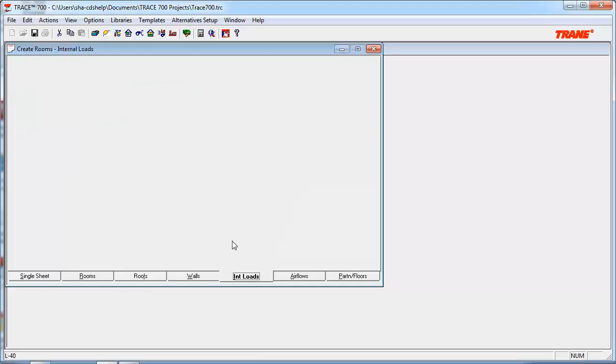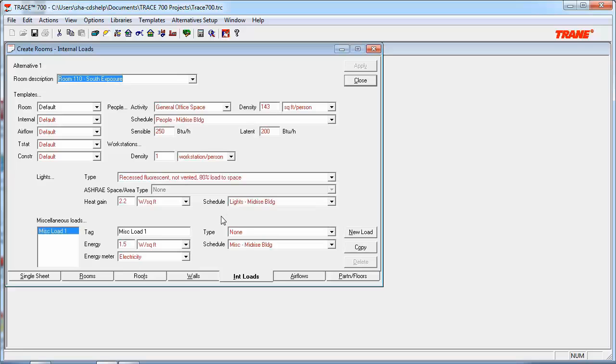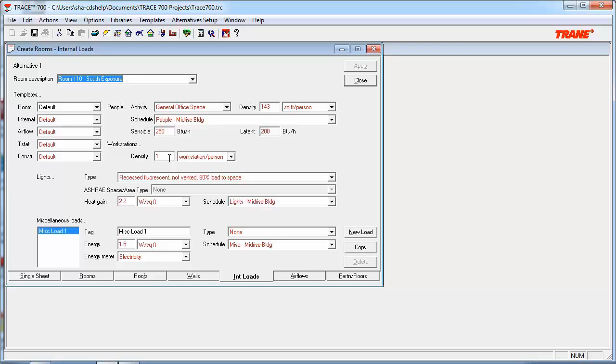Next, let's move on to the Internal Loads tab. The only field to pay close attention to here for affecting the stratification of a space is the workstation's input. This field defines the number or density of computer workstations located in the room. For HVAC system types that rely on thermal stratification, such as UFAD, this value helps define the number of thermal plumes to derive that stratification.